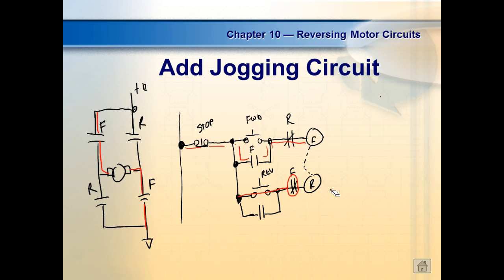If you got a fuse in there for the high voltage, you won't let the motor start for low voltage. That's a good shot. The problem is these overload sensors sense current. If I wire the motor for high voltage, it's going to pull less current. So if I have overload sensors for high current, for the low voltage, it won't trip. If I have the wrong overload sensor in there, then it either won't let the motor start or it will burn the motor up. So if you had the low voltage sensor and you wired it high voltage, it would burn the motor up, because those are designed to sense a higher current, right? You understand that? Because remember, horsepower is about what? Per watt. 746 watts per horsepower.